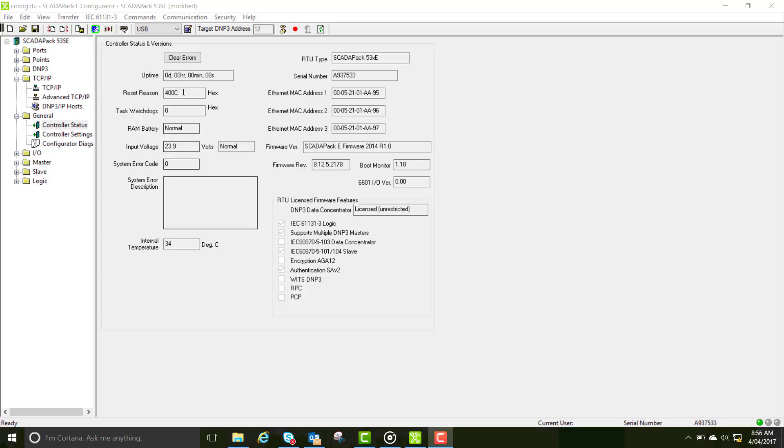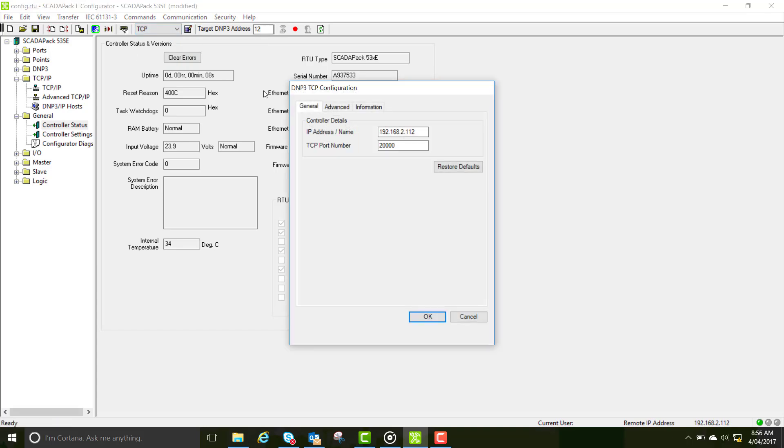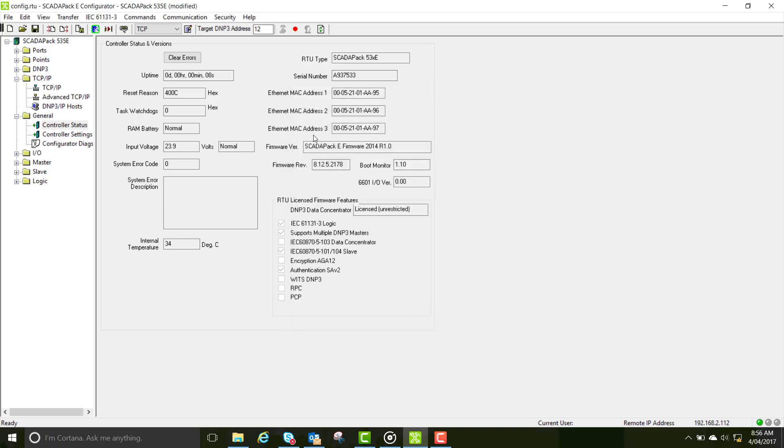Now go to the communication dropdown box, select TCP. Click on the communications box and enter your IP address and the TCP port number of the RTU is 20,000. Once you've done this, refresh your page again and you'll see the traffic light come back to green.